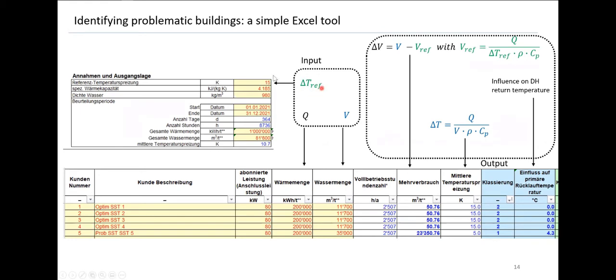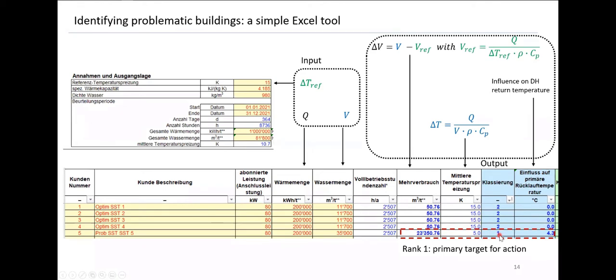To illustrate how it works, I entered the five-substation example into the tool. You input the reference delta T — here 15 degrees — along with consumption and used volume for each substation. The tool calculates the additional volume, V minus V ref, and the contribution each substation has on the average overall return temperature of the network. This exactly matches the value I computed by hand. We get a ranking — the bad substation has rank one, identifying it as a primary target for action.